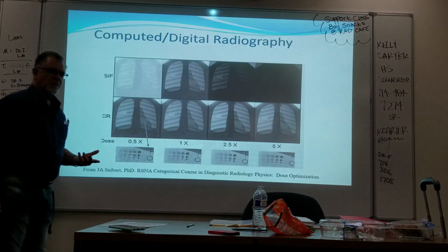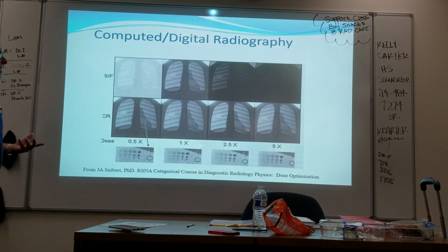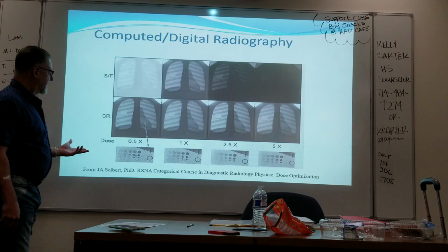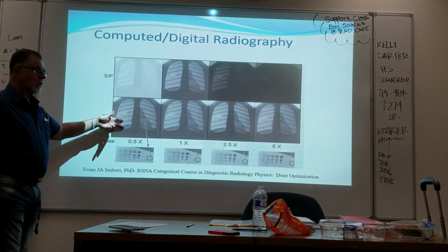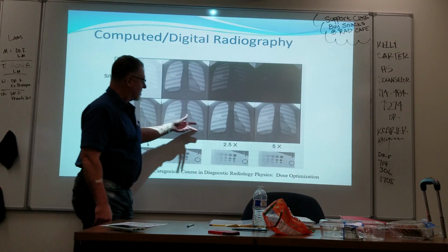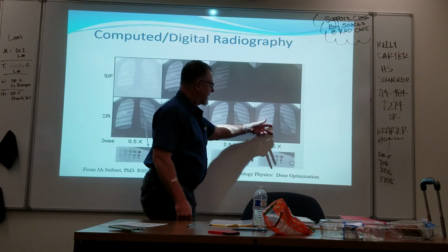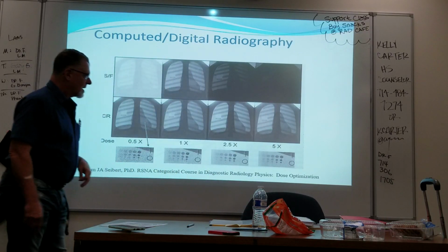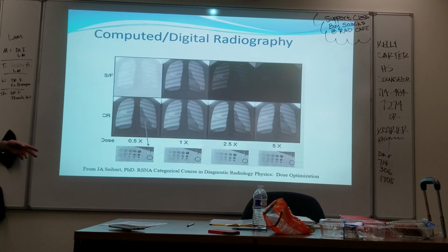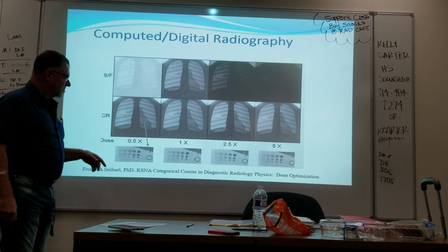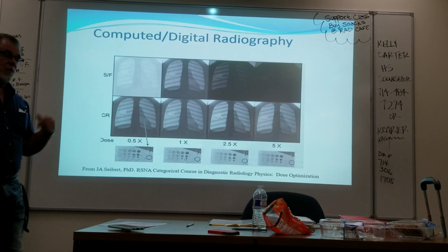But on a digital system where contrast can be artificially manipulated, you can take an inherently insufficient exposure and make it look okay visually, or overdose by quite a considerable amount. You have no idea. Now, you're supposed to be looking at the numbers, so whether it's the exposure index or whatever identifier the system that you're using uses, you can use that to see if it's out of range.